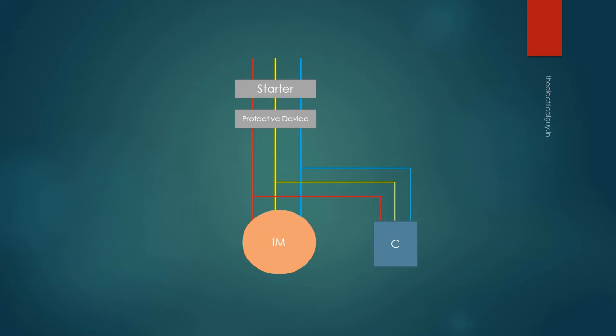Capacitor bank and the load can use the same protective device against overcurrent as shown in the figure, and can be connected and disconnected simultaneously. This type of power factor correction is advisable for large loads which remain connected to the system for a long time.